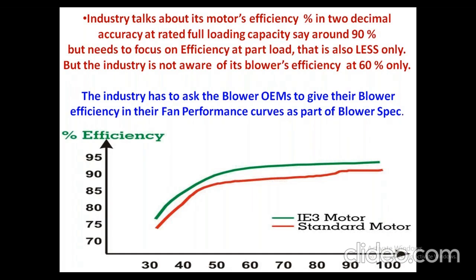The textile mill talks about motor efficiency: 92.3, 91.5, 91.67, like that. They talk in terms of two decimals for a motor, but none of the textile mills talks about blower efficiency, because we have not measured the static pressure for any of the given blowers. Maybe it's an axial fan or a blower, and the efficiency calculation is not done from the OEM, it has not reached the textile mill.